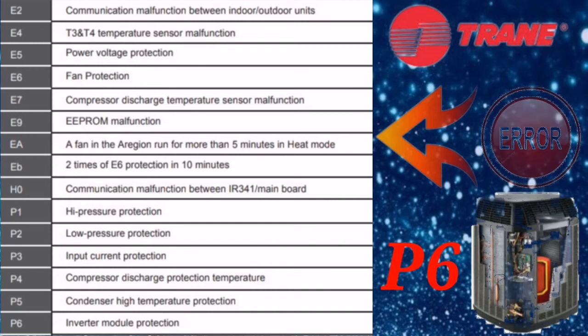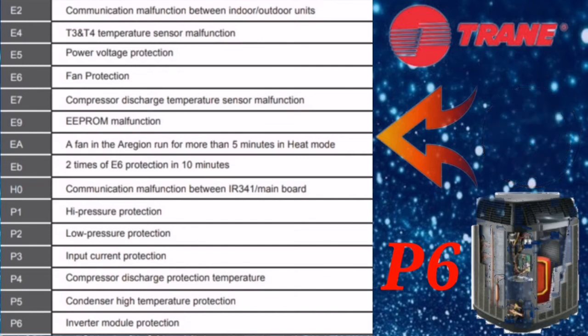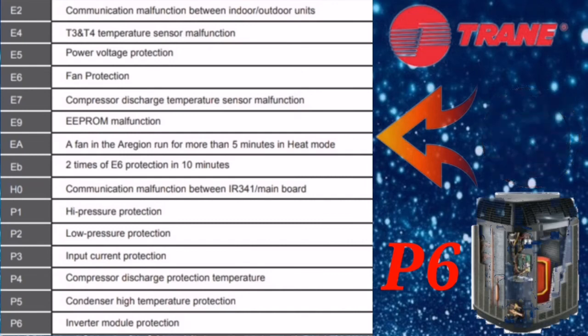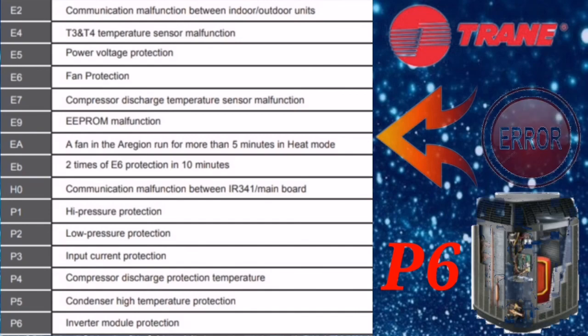The next error code is P6, which means inverter module protection. In 12,000 and 18,000 BTU units, the main PCB, rectifier, and inverter module are all combined on one PCB — change the outdoor PCB and your unit will be in working condition. For 24,000 BTU and above, there is a separate main PCB and inverter module — in that case, change the inverter module specifically and your unit will be in working condition.